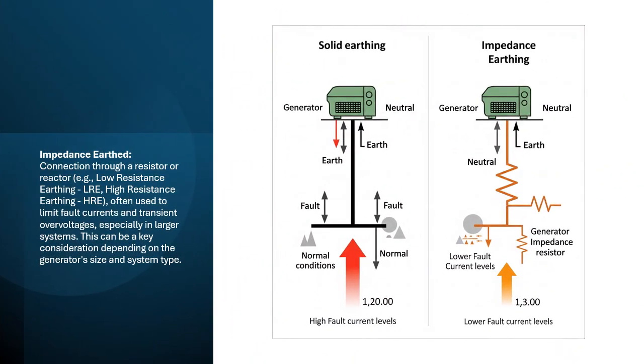Impedance earthed. Connection through a resistor or reactor, e.g., low resistance earthing, LRE, high resistance earthing, HRE, often used to limit fault currents and transient overvoltages, especially in larger systems. This can be a key consideration depending on the generator's size and system type.